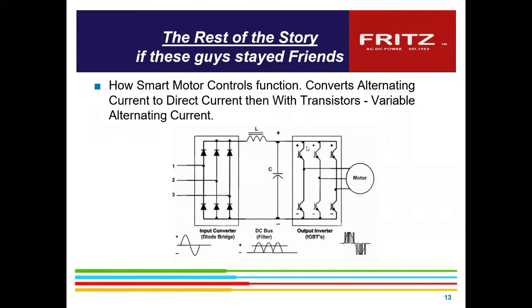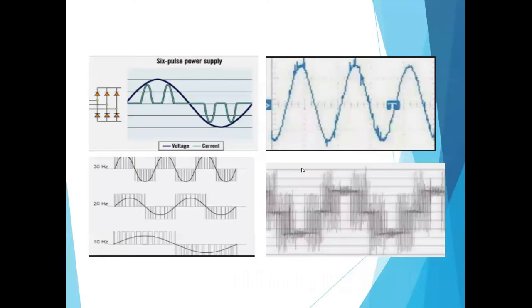And then with IGBT transistors on the backside, they're refiring what they call PWM. So it's actually not a totally true looking sine wave. It actually has pulses in it. There are some factors you have to be aware of when you're doing this, and that's where you get issues with motors. So it's good to definitely know what motor you have and what's going on.